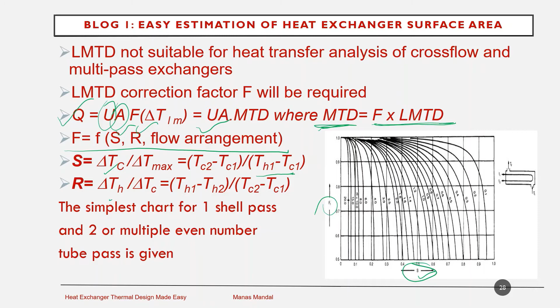S is nothing but delta Tc, difference in cold fluid temperature, and delta T max. Delta T max is the temperature difference of hot fluid inlet temperature and cold fluid inlet temperature, which is the maximum temperature difference in any exchanger. Similarly, R is the ratio of hot fluid differential divided by cold fluid differential: TH1 minus TH2 divided by TC2 minus TC1. The chart on the right side is the plot of S versus R to give us F. The x-axis is giving us S. These curves are R values, and y-axis is F. So first we have to calculate S, which we will plot on R, and that will give us F.